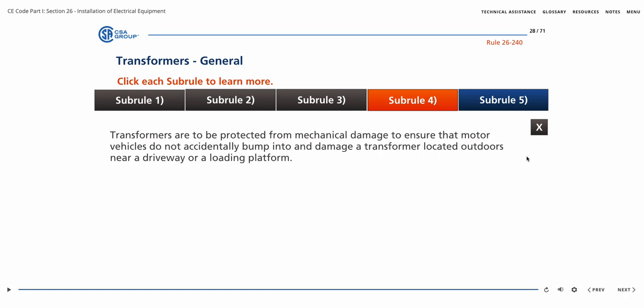Subrule 4 requires that transformers are to be protected from mechanical damage to ensure that motor vehicles do not accidentally bump into and damage a transformer located outdoors near a driveway or a loading platform.